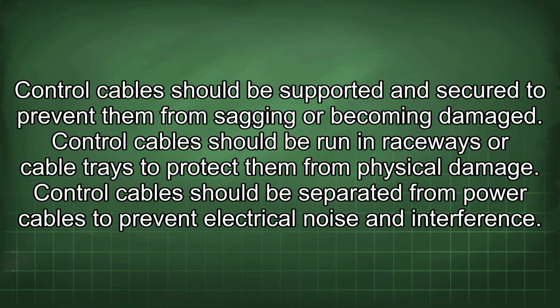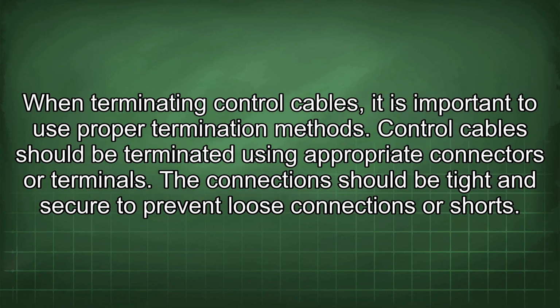Control cables should be supported and secured to prevent them from sagging or becoming damaged. Control cables should be run in raceways or cable trays to protect them from physical damage. Control cables should be separated from power cables to prevent electrical noise and interference. When terminating control cables, it is important to use proper termination methods. Control cables should be terminated using appropriate connectors or terminals. The connections should be tight and secure to prevent loose connections or shorts.